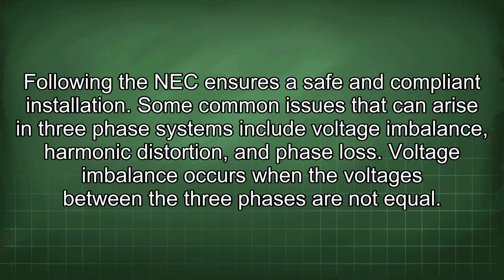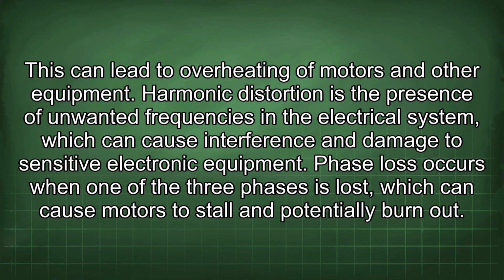Some common issues that can arise in three-phase systems include voltage imbalance, harmonic distortion, and phase loss. Voltage imbalance occurs when the voltages between the three phases are not equal. This can lead to overheating of motors and other equipment. Harmonic distortion is the presence of unwanted frequencies in the electrical system which can cause interference and damage to sensitive electronic equipment.